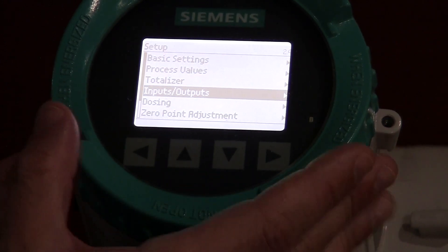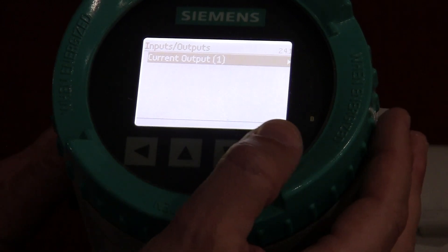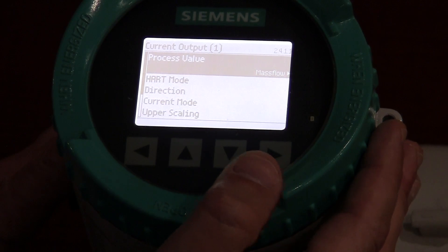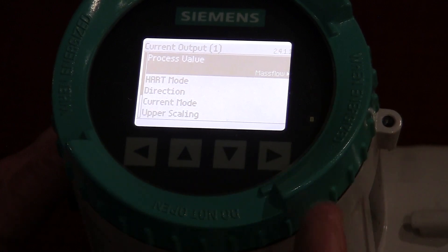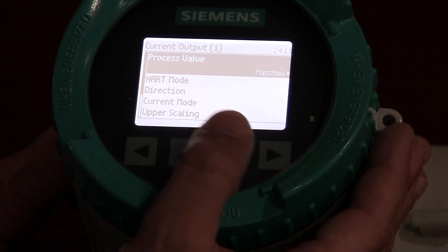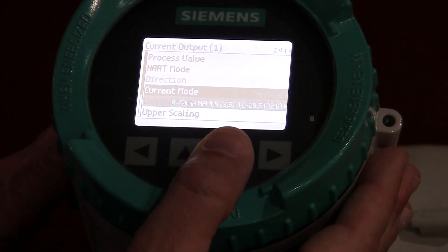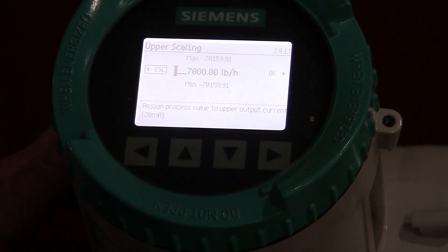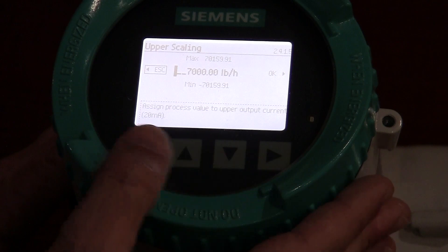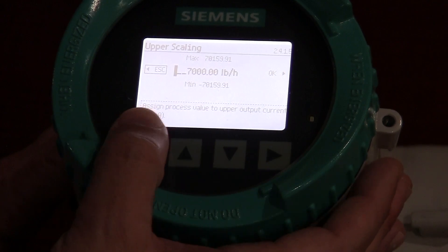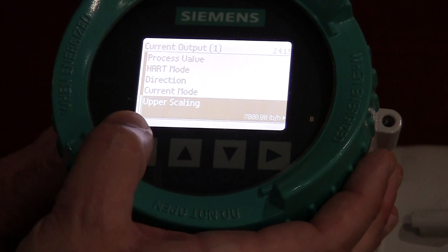Here's where you're going to set your inputs or outputs. This particular transmitter has one 4 to 20 output. We're going to go in here — it's going to say you have one current output. I'm going to select that and assign it to what process value you want it related to. In this case it's mass flow, but I could theoretically set that for temperature or density. Direction — there's a positive and negative direction based on which way the meter is installed. You can also set your upper scaling. Right now I'm set 0 to 7,000 pounds per hour, which is going to be my 4 to 20 for mass flow. This is exactly like our other Siemens products to go back and forth in the menus.